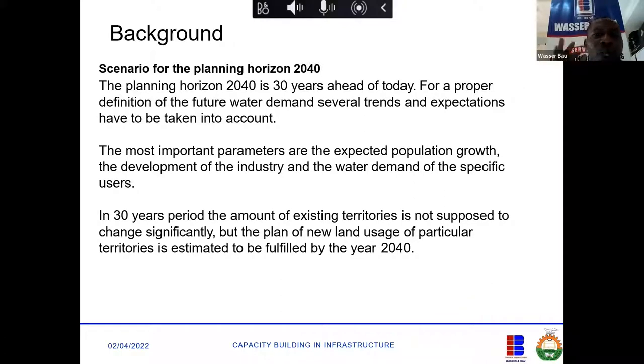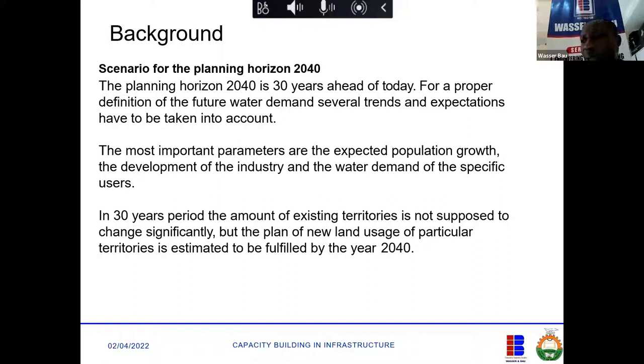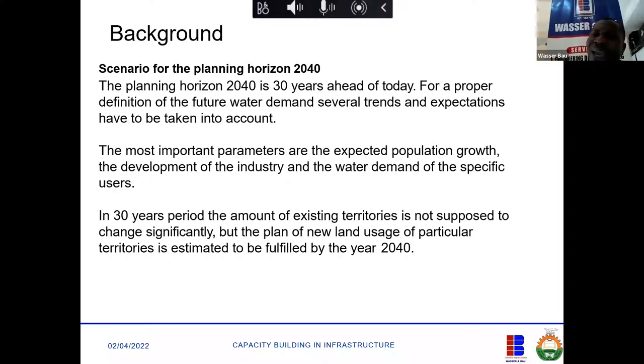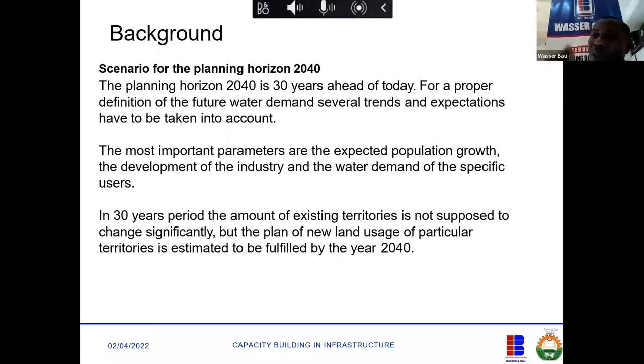We are planning for 30 years, because you don't plan for today, you plan for the future, and the parameters you use for planning are the parameters of the future. If the current population is 100,000 and in 30 years I expect it to go to 150,000, the value I'll use for my design will be 150,000. Then if I expect a new university, a new school, a change of land use affecting 20% of my development, I calculate 20% of the population and add it - so maybe 170,000. That becomes my population equivalent, PE, which is a very important parameter for your design.